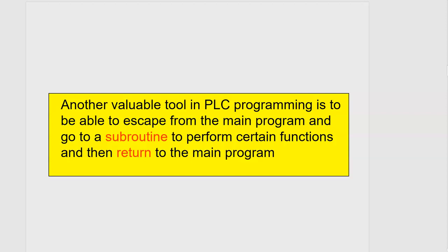Now, I really like this method, and the reason is, since the subroutine itself is a program that works regardless of what's happening around it, regardless of what's happening in the main program, you can do a couple things. Number one, it makes maintenance really easy. If you need to change something inside the subroutine, you can change it, and since the subroutine runs independently, you don't have to worry about it affecting other parts of the main program, which can be a huge thing if you have a really long program. Another reason that I like it is this ideal in computer programming or computer science. There's something called reuse.